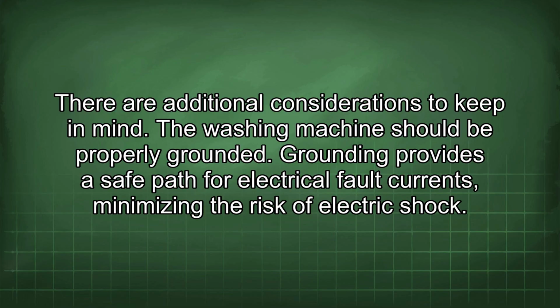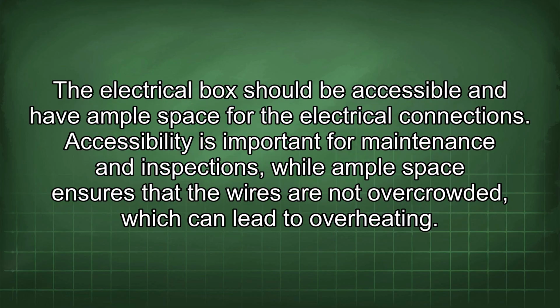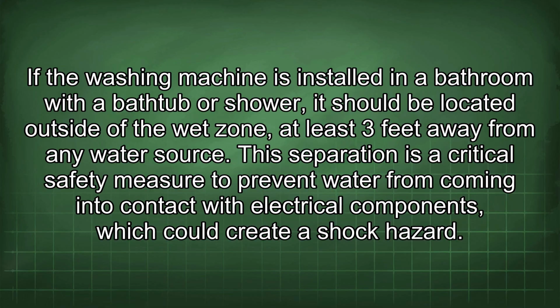The washing machine should be properly grounded. Grounding provides a safe path for electrical fault currents, minimizing the risk of electric shock. The electrical box should be accessible and have ample space for the electrical connections. Accessibility is important for maintenance and inspections, while ample space ensures that the wires are not overcrowded, which can lead to overheating. If the washing machine is installed in a bathroom with a bathtub or shower, it should be located outside of the wet zone, at least 3 feet away from any water source.